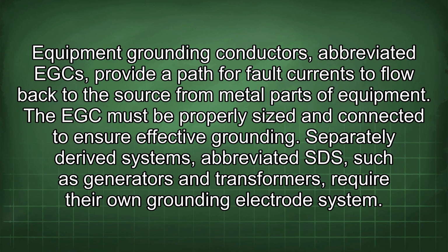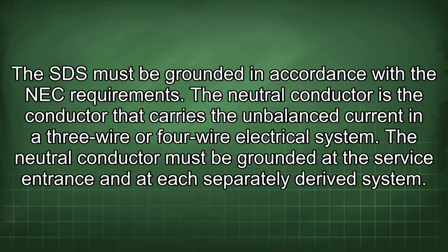Separately derived systems, abbreviated SDS, such as generators and transformers, require their own grounding electrode system. The SDS must be grounded in accordance with the NEC requirements. The neutral conductor is the conductor that carries the unbalanced current in a 3-wire or 4-wire electrical system. The neutral conductor must be grounded at the service entrance and at each separately derived system.